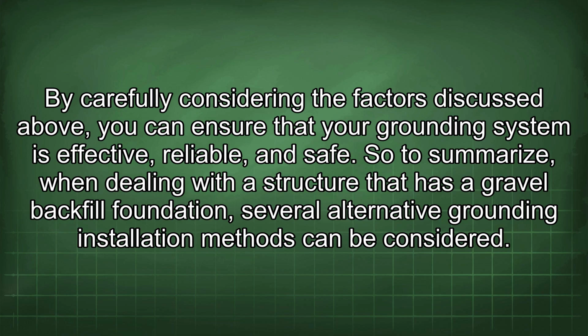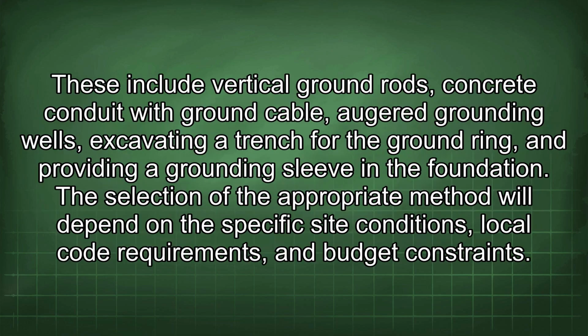So to summarize, when dealing with a structure that has a gravel backfill foundation, several alternative grounding installation methods can be considered. These include vertical ground rods, concrete conduit with ground cable, augered grounding wells, excavating a trench for the ground ring, and providing a grounding sleeve in the foundation. The selection of the appropriate method will depend on the specific site conditions, local code requirements, and budget constraints.